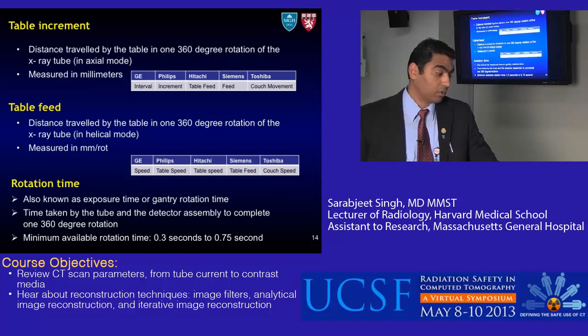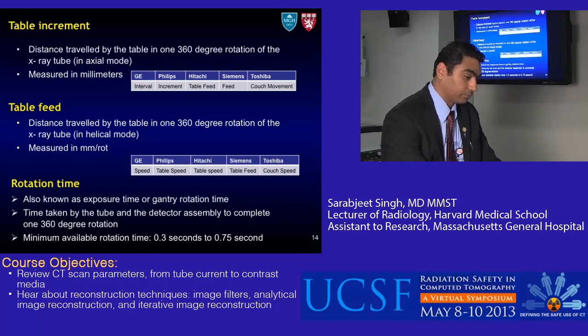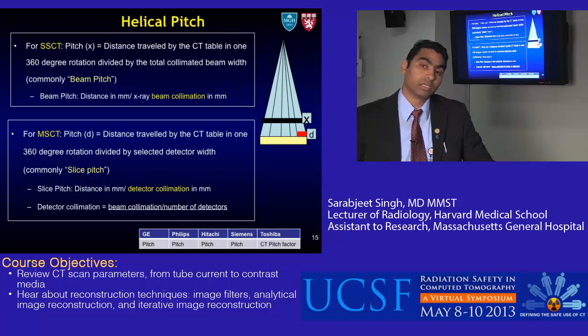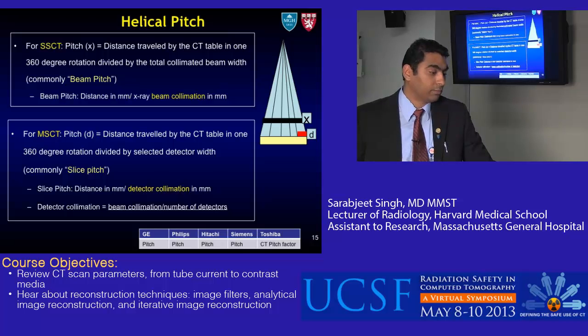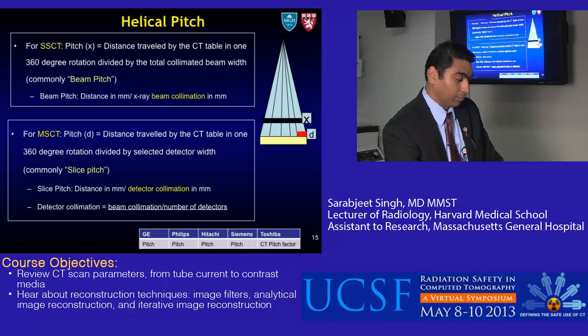Rotation time, also known as exposure time or gantry rotation time, is the time taken by the tube and detector assembly to complete one 360-degree rotation. Next is helical pitch. For single-slice CT, pitch is the distance traveled by the table in one 360-degree rotation divided by the total collimated beam width. For multi-slice CT, pitch is the distance traveled by the CT table in one 360-degree rotation divided by the selected detector width. Almost all vendors consistently call this pitch.